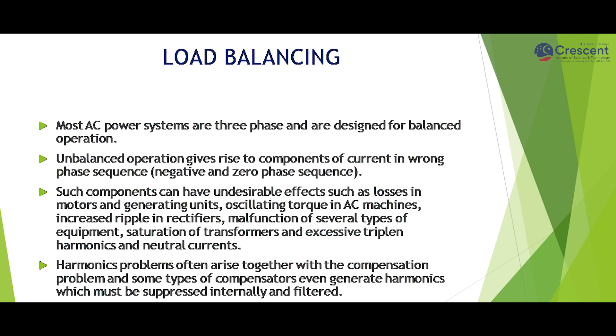Compensators are used locally where the load is connected. The next objective of load compensation is load balancing. Most AC power systems are three-phase and designed for balanced operation. Unbalanced operation gives rise to currents in the opposite direction, causing oscillating torques in AC machines, losses in motors and generating units, increased ripple in rectifiers, malfunction of several types of equipment, saturation of transformers, and excessive triple-n harmonics and neutral currents.